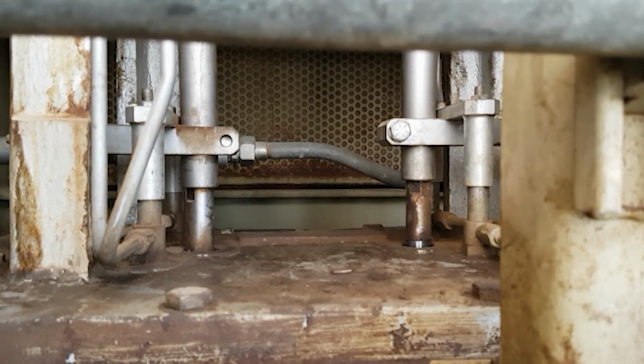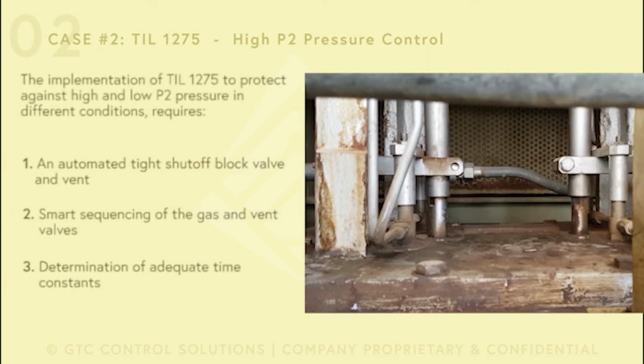You see, we did the staggering of these valves and the results were phenomenal. The customer was so happy when he saw the results. I mean, he said this unit never started so smoothly. All four flame detectors detected flame within 8 seconds into the firing timer. He looked like a kid that opened the back door to the backyard on Christmas Day and found out that Santa left him a pony. He was beaming. Let's play the video again.